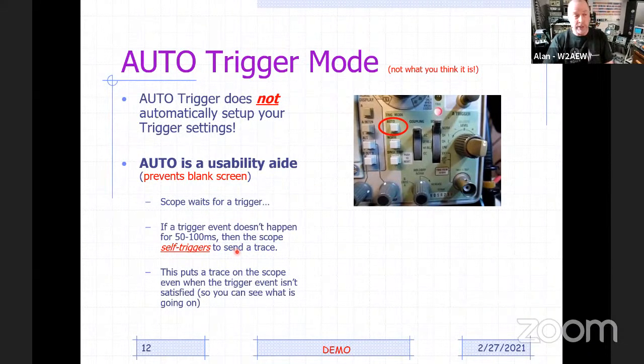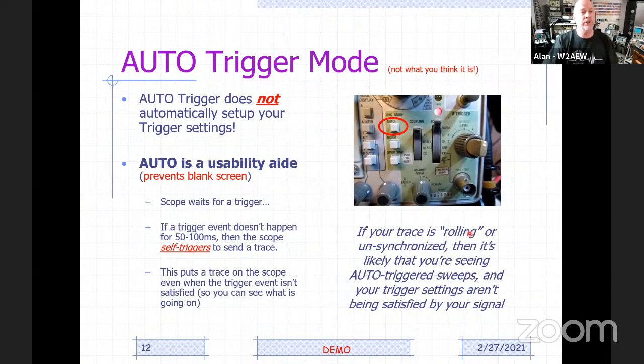And to give you an aid to figure out how to correct what you might have set up wrong in the trigger. Otherwise, if you have the trigger set up wrong, you'd have a blank screen. So it really is kind of an auto free run. Okay, but it's an auto free run that will switch back to a triggered mode once the trigger condition gets satisfied. Okay, so if your trace is kind of rolling or is unsynchronized, it's likely that you're seeing these auto triggered sweeps and you're not actually triggering on your signal itself.